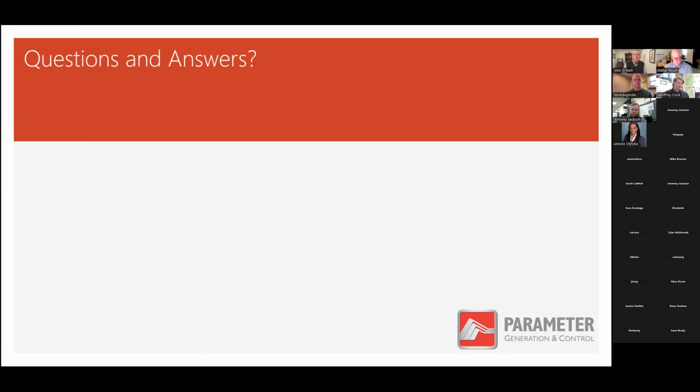In the event of a heater failure, knowing how to navigate the machine's controller and checking several of the various parameters that you can see in the user interface. Most failures can be determined by taking a few data readings from the interface. And that way, through your familiarity with the machine and how it works, you can know within an hour the parts you need, the service you need, or what your mitigation plan will be.